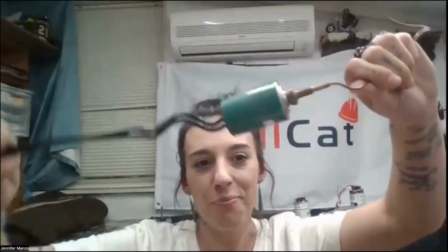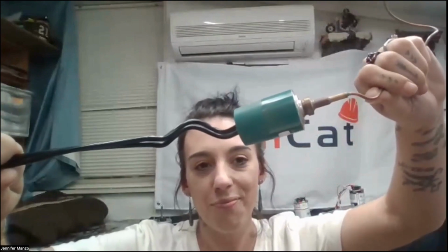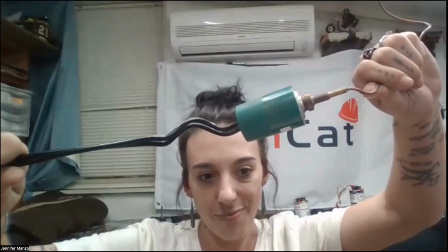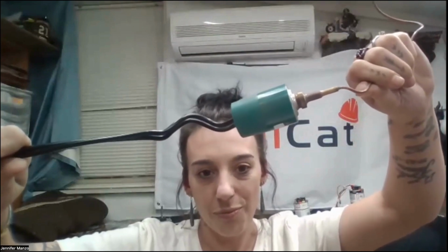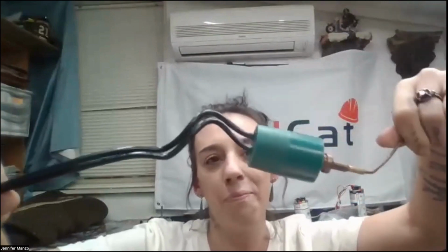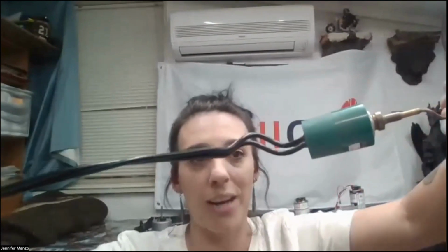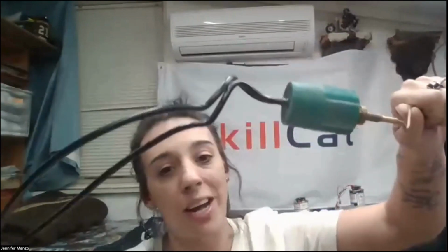Its job is to protect the system from pressure too high or too low. Yep. The compressor, exactly. It's to protect the compressor. Protect the compressor at all costs. This one did. It fried, and that is why it's no longer in the system it was in. So this one did its job, and it sacrificed itself, but that's okay with me as long as I didn't sacrifice a compressor that was like 25 years old. So that's why that was here.